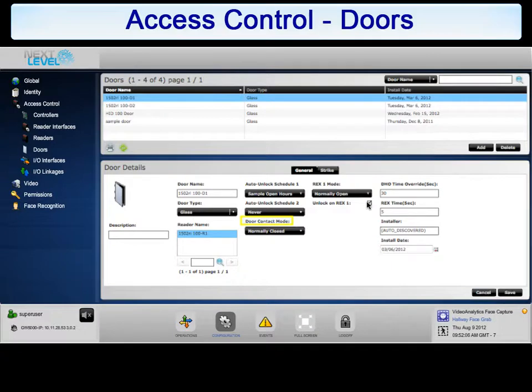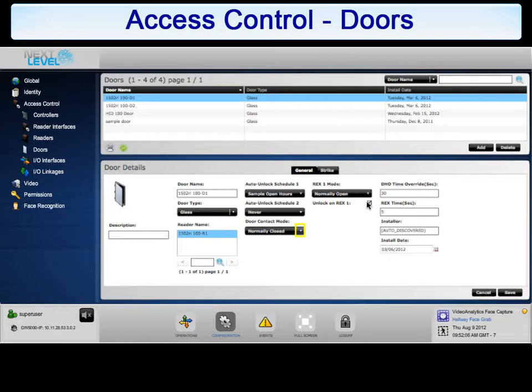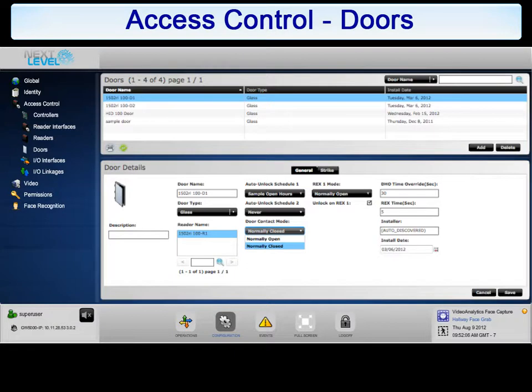The door contact mode should match the physical wiring of the door contact: normally open or normally closed. The system uses this setting to determine if a door has been opened or used. Select the arrow next to the drop-down box to select the correct door contact mode. Choose normally open or normally closed to continue.